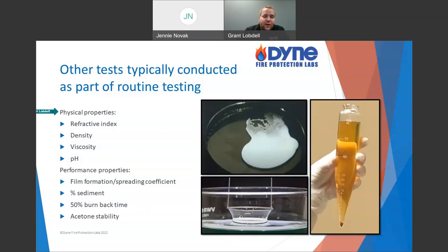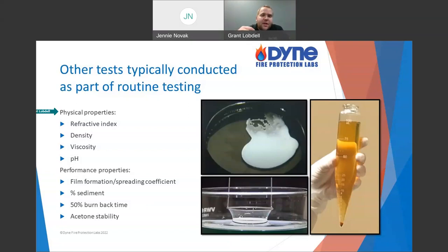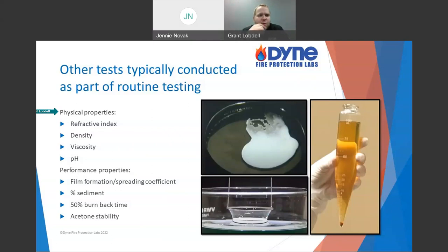Now let's jump to physical properties. These are more like attributes of the foam — how it looks right now versus how it was. None of these physical properties that we check are necessarily going to fail a foam on their own, except in very extreme circumstances. These are just a peek into how the foam is doing compared to how it was. The main ones checked are refractive index, density (sometimes expressed as specific gravity), viscosity, and pH.